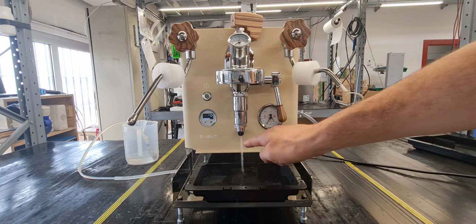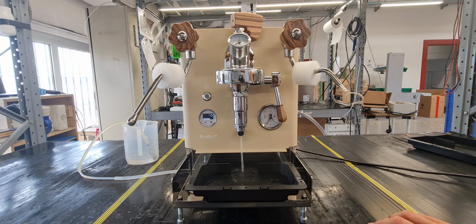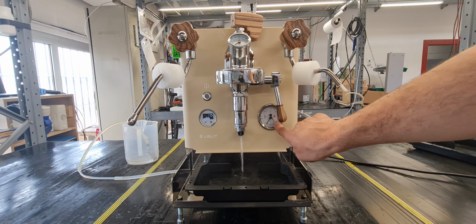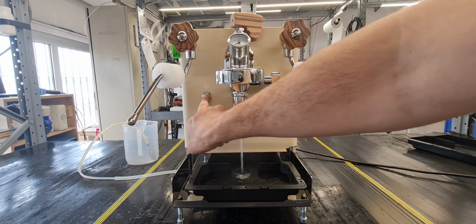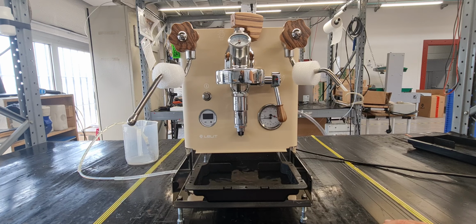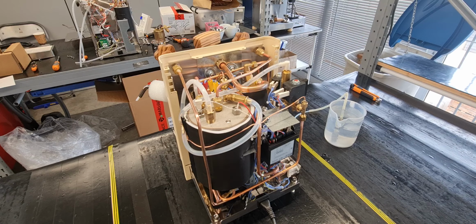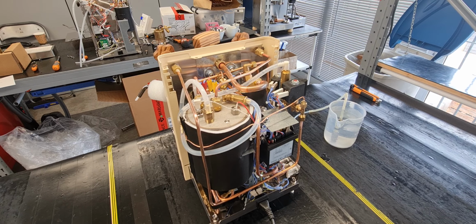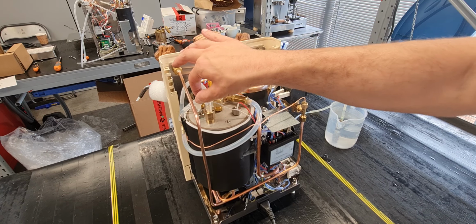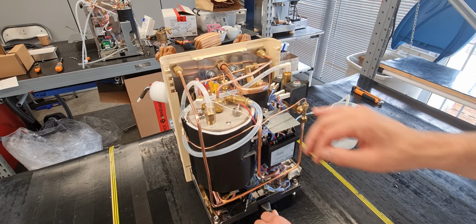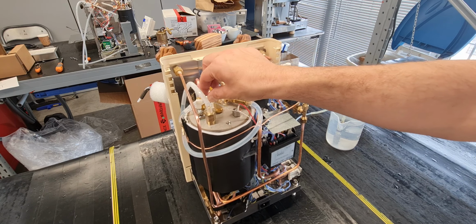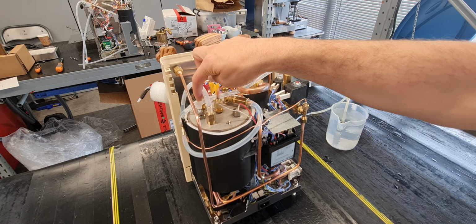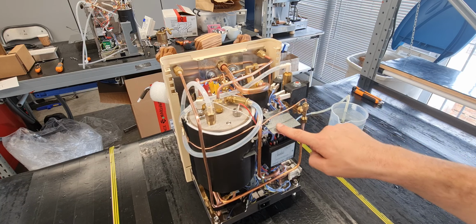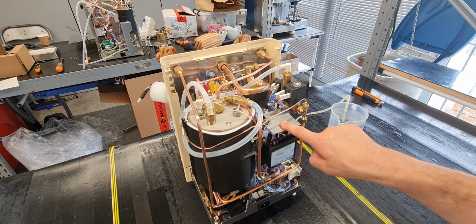And this is the issue. Now, as you can see here, the pressure gauge shows you that the steam boiler is full of water. In this case, the first thing to do is remove the power cord. First of all, remove this wire and connect this wire to the land, to the chassis of the machine.